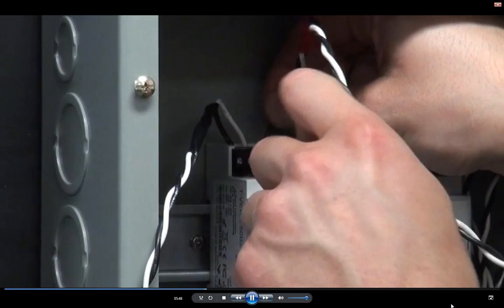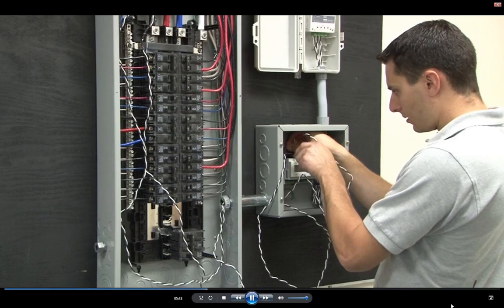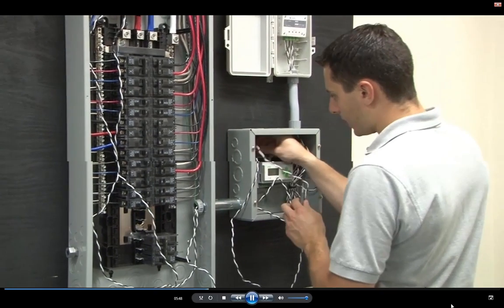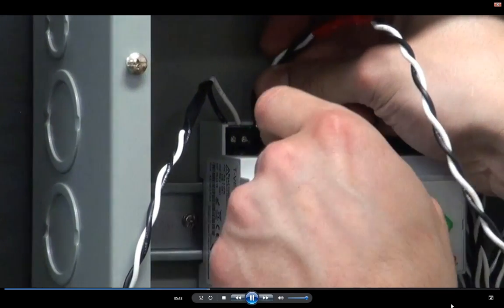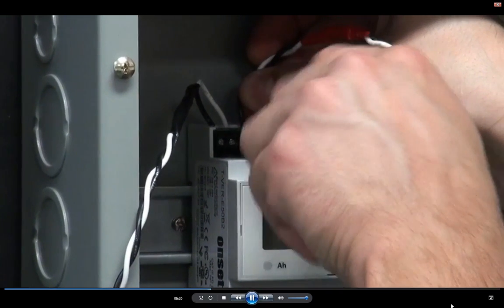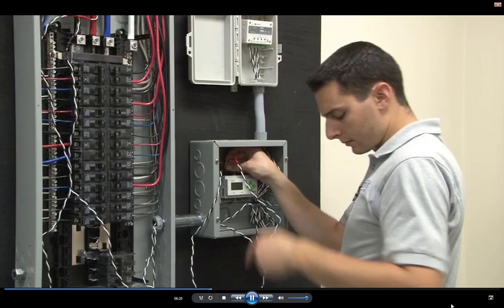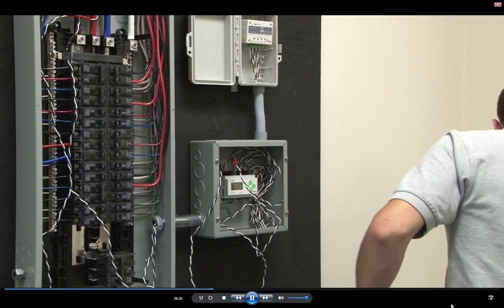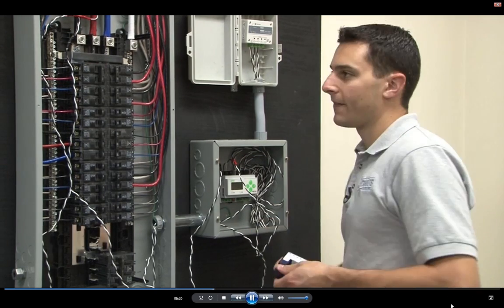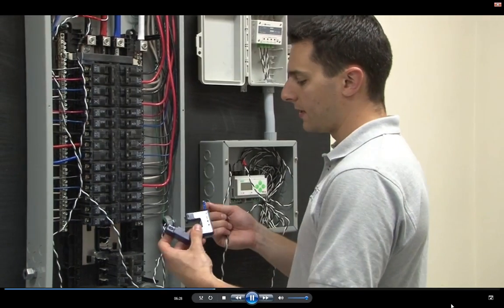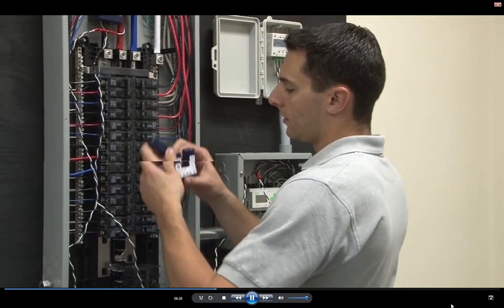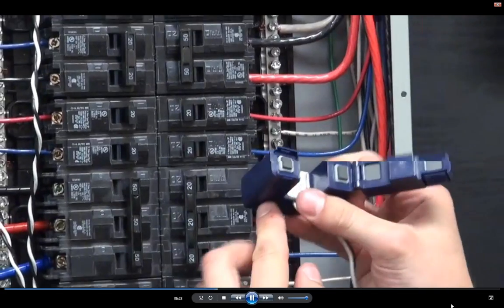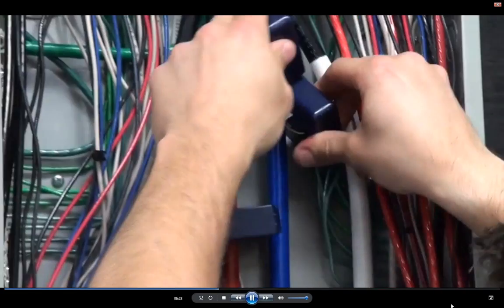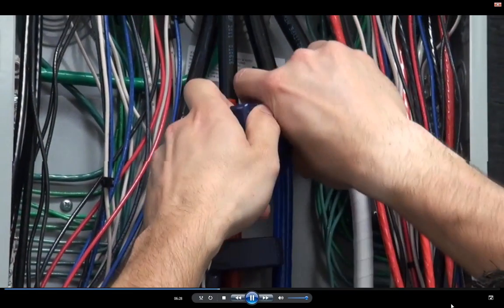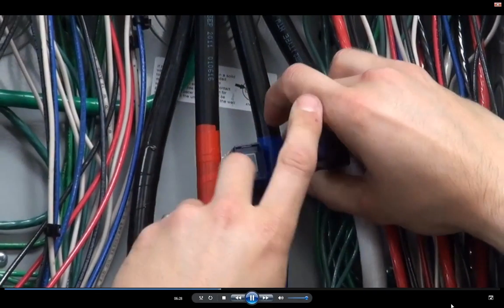The black conductor connects to the negative terminal, and the white conductor connects to the positive terminal. Our final CT is the blue phase C CT. Once again, we line up the arrow with the source, connect the CT around the conductor, and clip it closed.